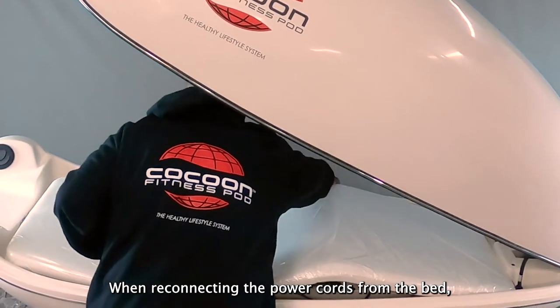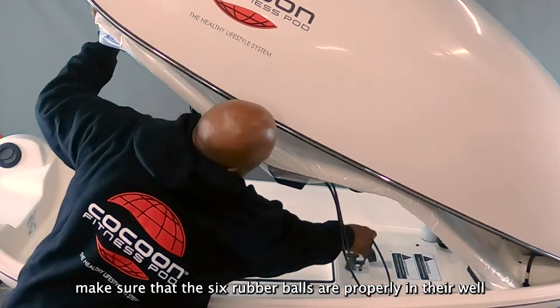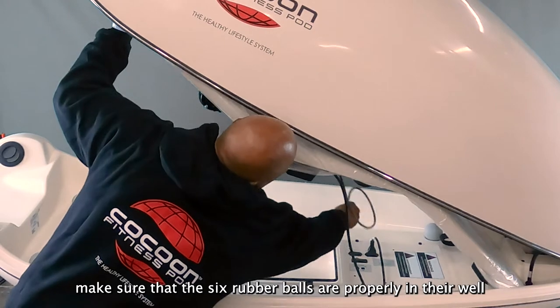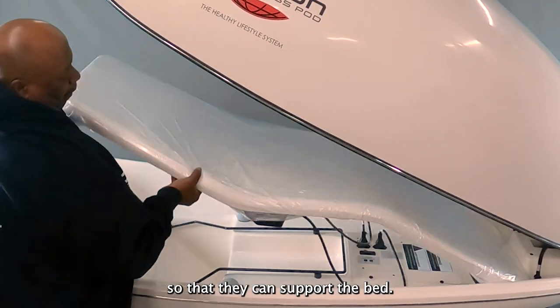When reconnecting the power cords from the bed, make sure that the six rubber balls are properly in their well so that they can support the bed.